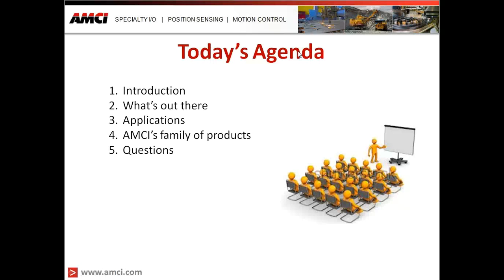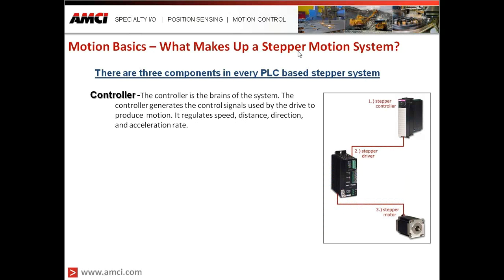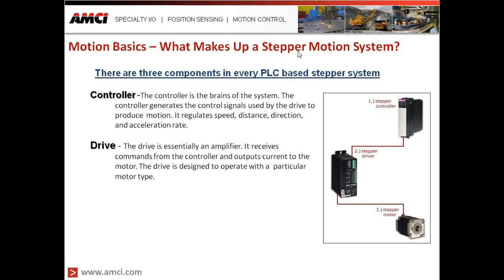There are three components in every PLC-based stepper system. The controller is the brains of the system — it generates the control signals used by the drive to produce motion, and it regulates speed, distance, direction, and acceleration rate. In a traditional PLC system, the controller is typically a plug-in card or a remote IO interface. Some PLCs provide an onboard pulse train output, or PTO, for simple stepper control.